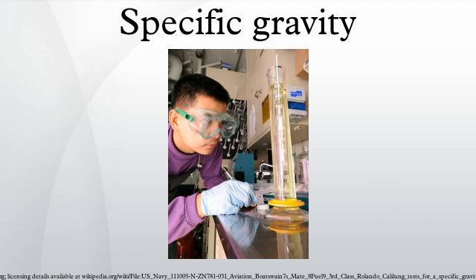Buoyant force transducer: the buoyancy force produced by a float in a homogeneous liquid is equal to the weight of the liquid that is displaced by the float. Since buoyancy force is linear with respect to the density of the liquid within which the float is submerged, the measure of the buoyancy force yields a measure of the density of the liquid. One commercially available unit claims the instrument is capable of measuring specific gravity with an accuracy of ±0.005 SG units.